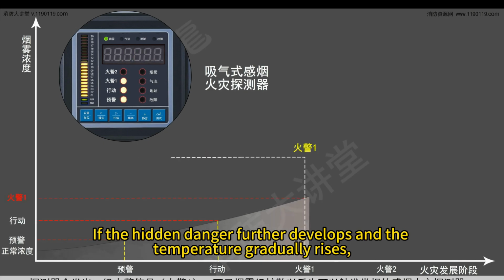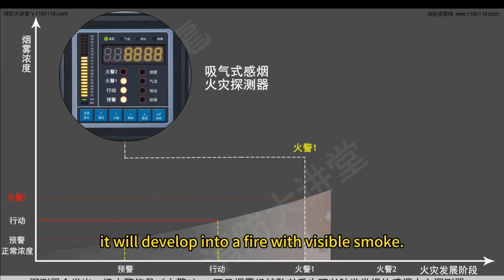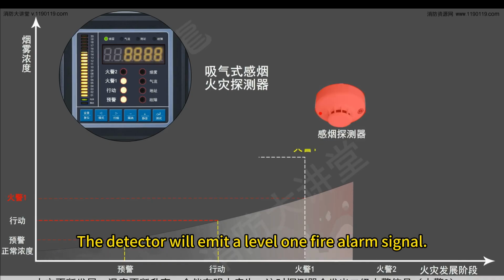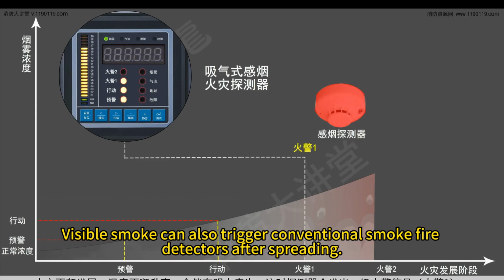If the hidden danger further develops and the temperature gradually rises, it will develop into a fire with visible smoke. The detector will emit a level 1 fire alarm signal. Visible smoke can also trigger conventional smoke fire detectors after spreading.